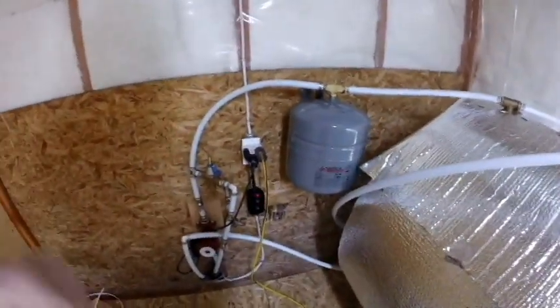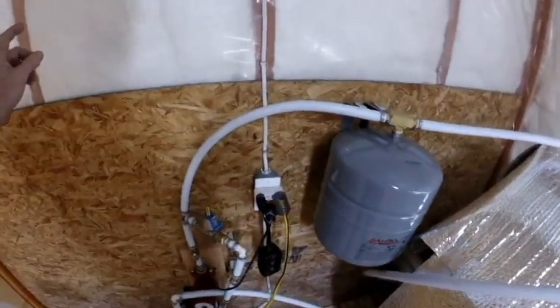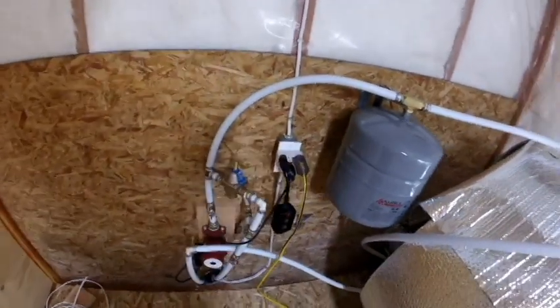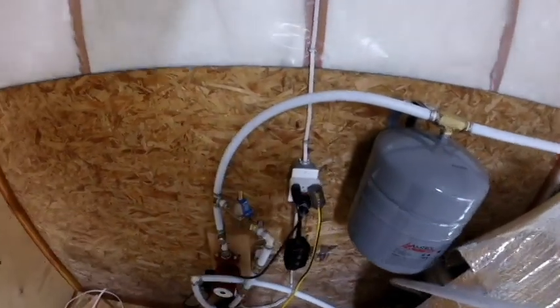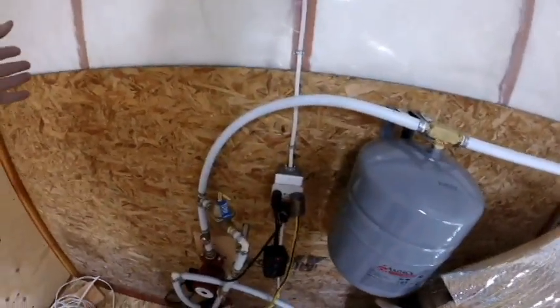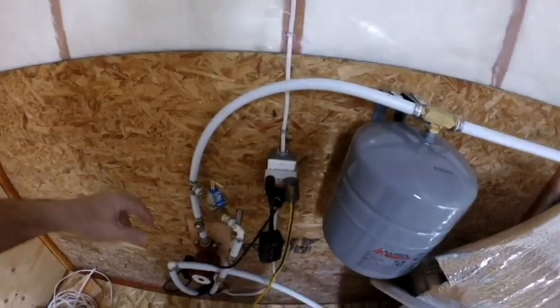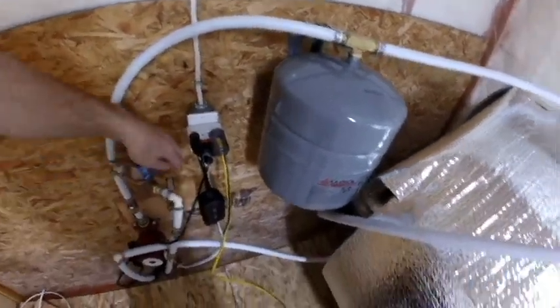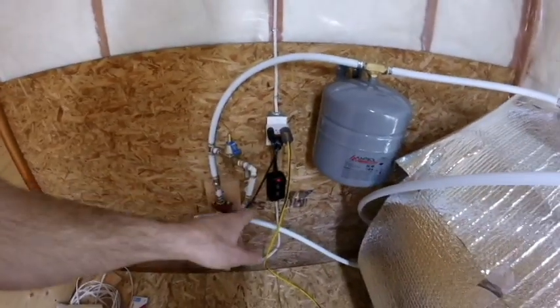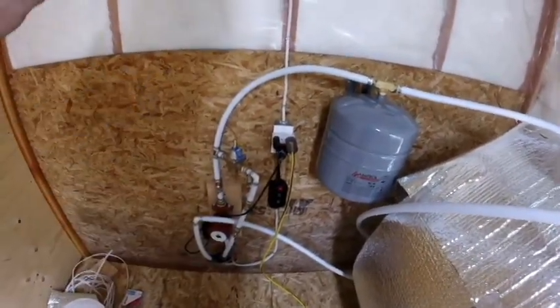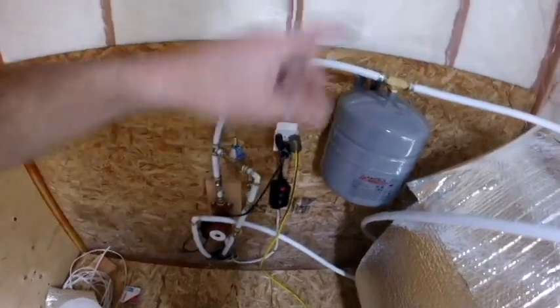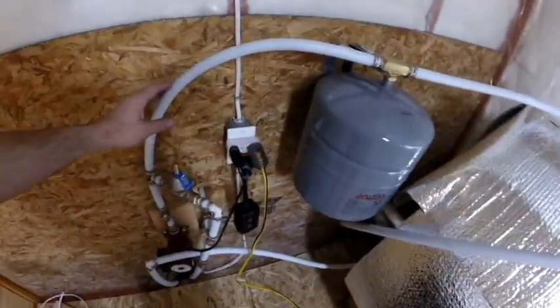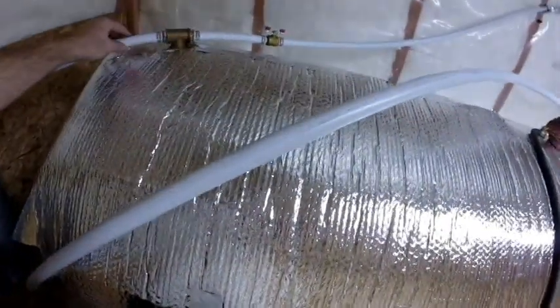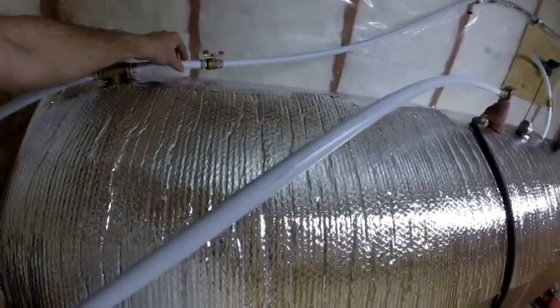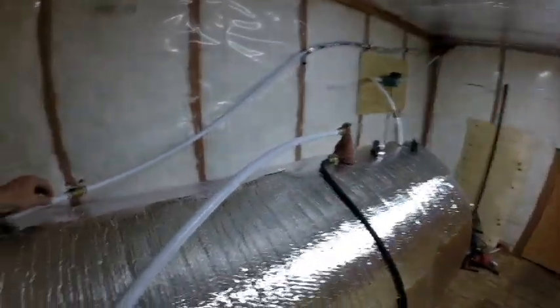Now, the way this system works is anytime the boiler in the house calls for water, or calls for heat per se, any one of the thermostats that calls for heat in the house switches on the circulation pump in the house. At the same time, it switches on this circulation pump out here, and I did that by running the electrical line from the boiler in the house. So when that pump runs, this pump runs, flowing the water in. Anytime this pump runs, it's pulling water out of the tank. But anytime this pump runs, the hottest water in the system is coming directly off the boiler outside.